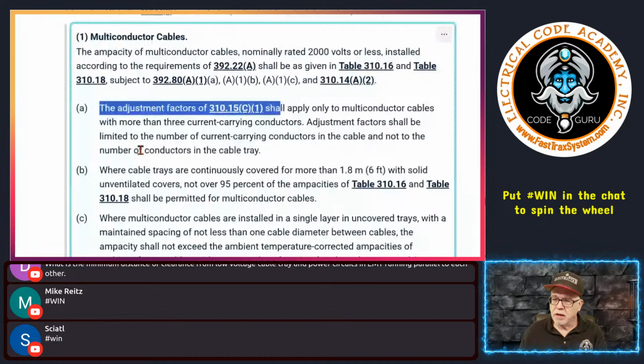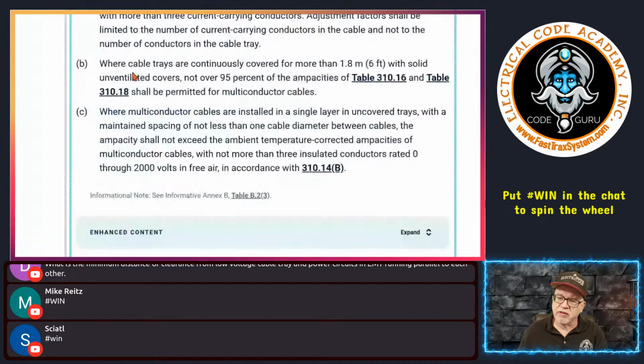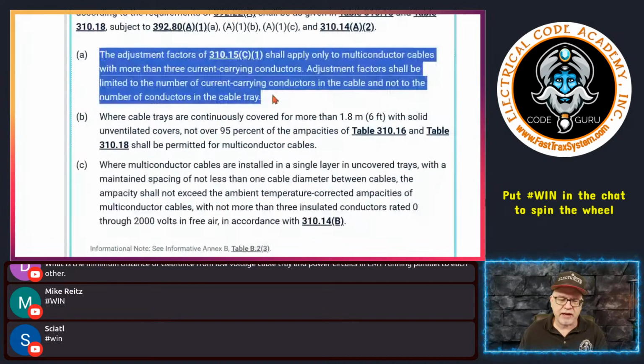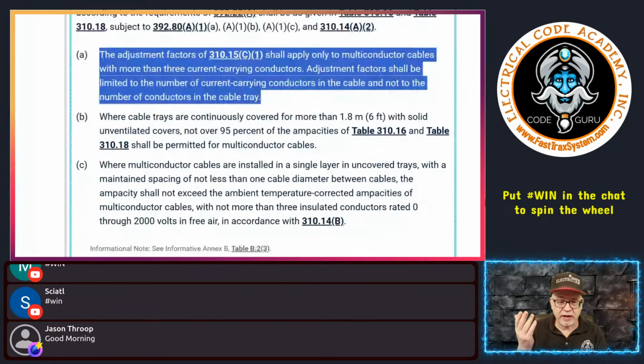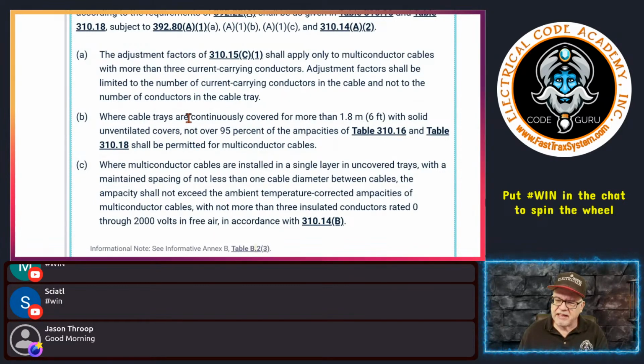Okay. All right. B. Now, B says, where the cable tray is continuously covered. So again, this one implies that the previous one is an uncovered application, so an uncovered cable tray. Good morning, Jason. Uncovered cable tray. This one is specifically talking about a continuously covered cable tray of a certain length. So it says, look, where a cable tray is continuously covered for more than 6 feet with a solid unventilated cover. And where we maybe have something like this?